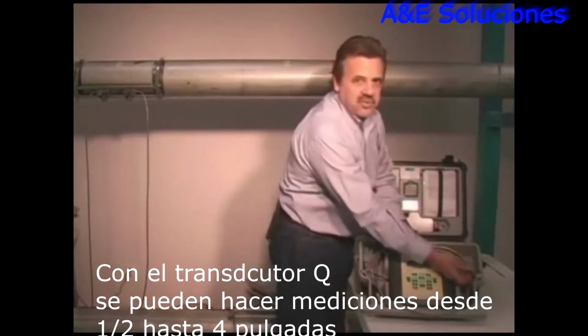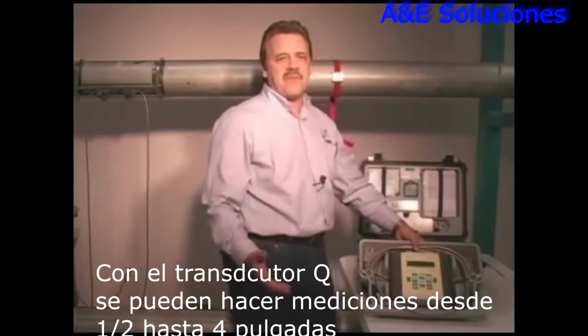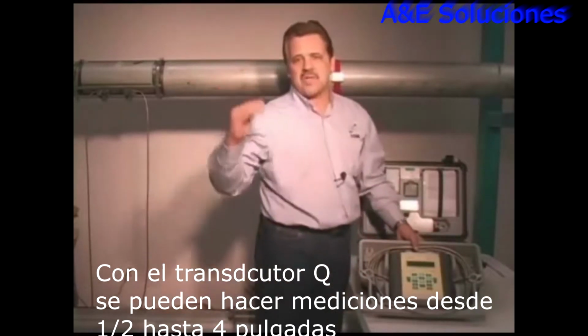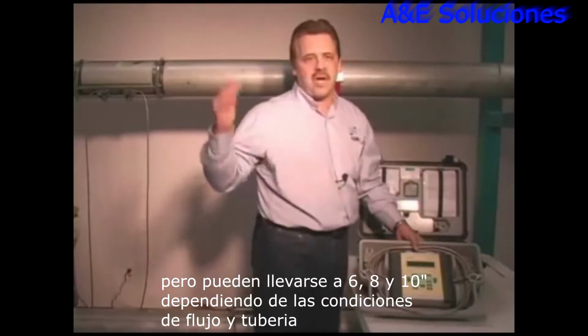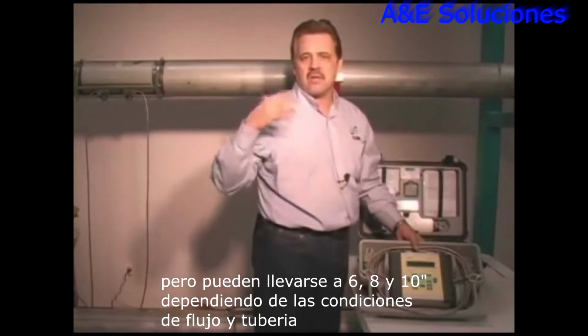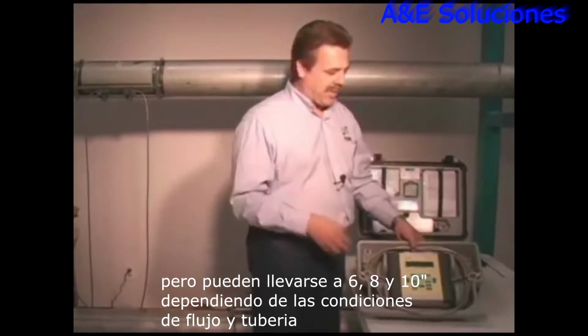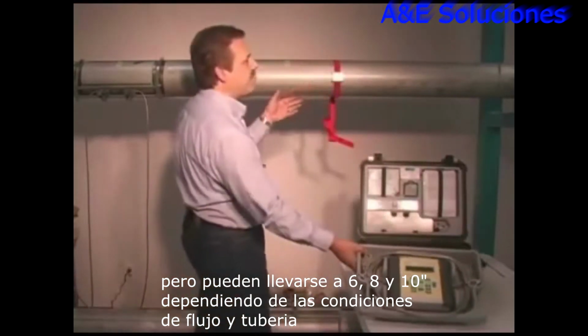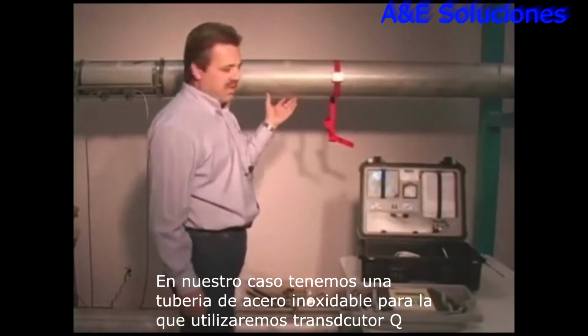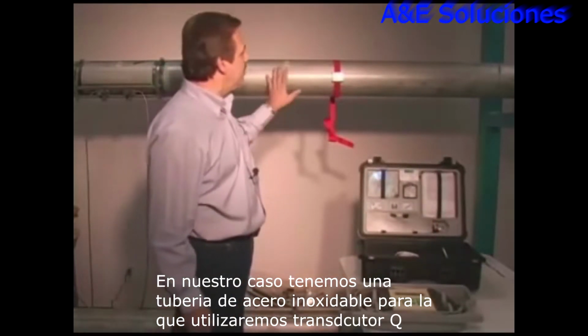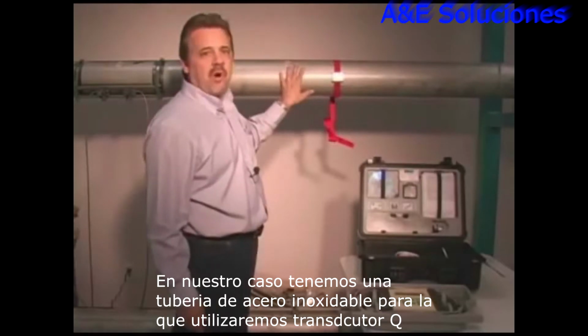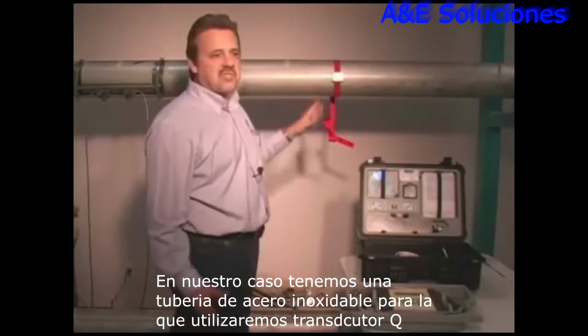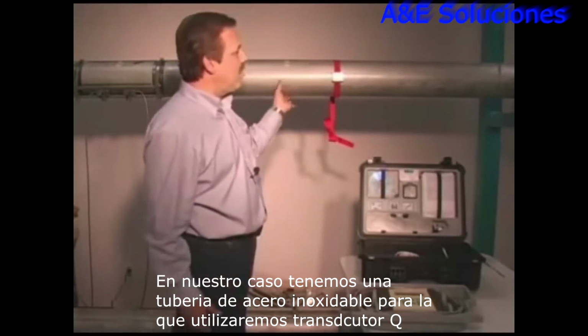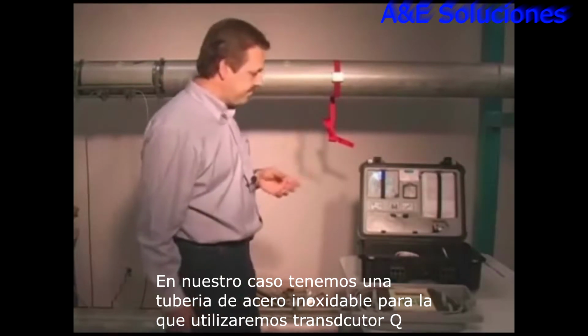With your Q-size transducer, you can cover from 1/2 inch to 4-inch pipes, and that can be stretched up to slightly larger diameters, 6, 8, 10-inch, depending on the condition, again, of the pipe. Here we have some pretty good pipe, stainless pipe. The Q-size transducers would work quite well if this were a 12-inch. It happens to be a 6-inch. The Q-sizes would work well on this because you'd still get a strong signal.